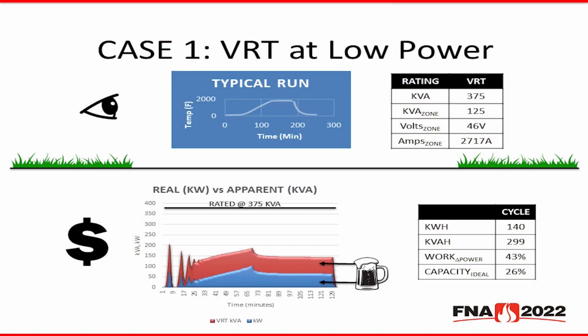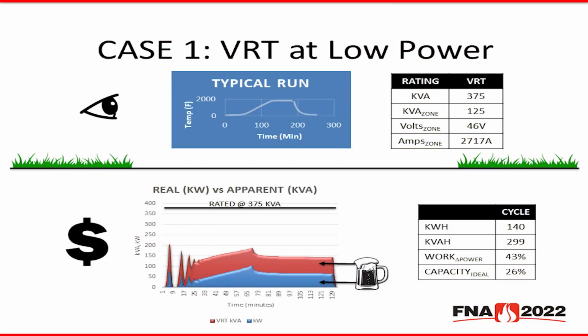The best way to understand this is to look at the total kWh versus the kVAh. For this run, the total kWh was 140, and the total kVAh was 299. That means that only 43% of power to this application is actually doing work. That's about 60% foam on top of the beer. Another important note to make on this graph is the rated capacity of the furnace. This was rated at 375 kVA. The maximum point in this run, in terms of kW, was 120 kW. So in other words, this furnace was operating at 26% of its maximum rated electrical capacity.